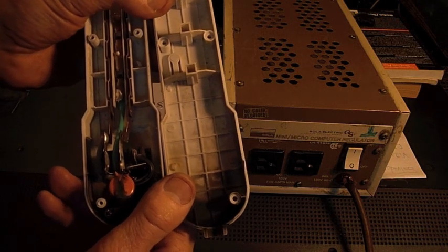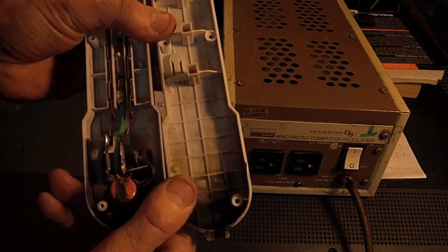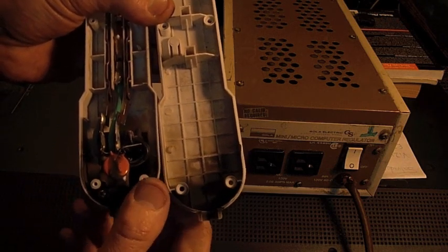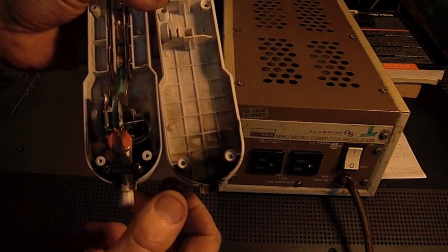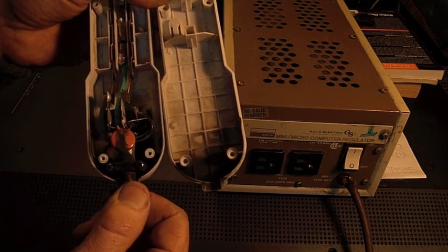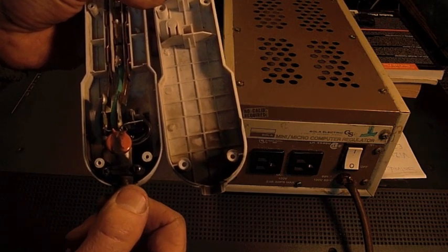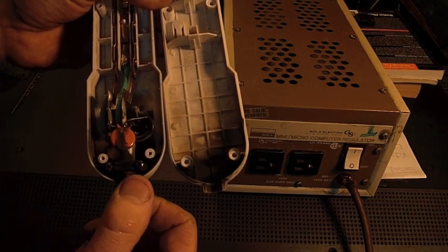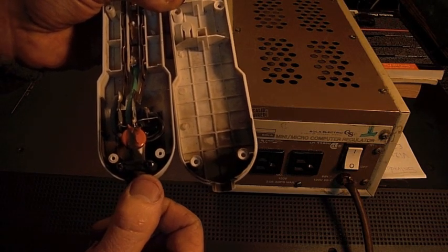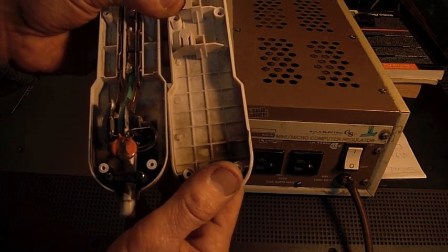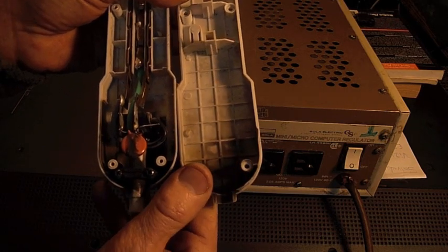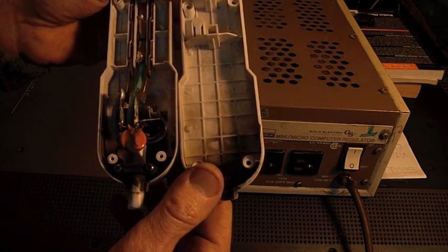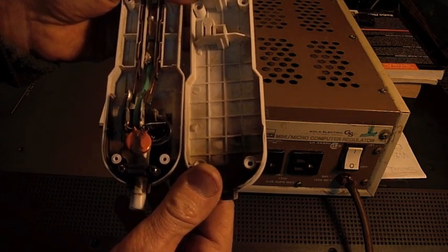And I went out to her house and checked things out. I measured the power coming out of the outlet and I measured about 245 volts out of some of the outlets. And I told her it looked like she was missing a neutral line on the service panel coming into the house.